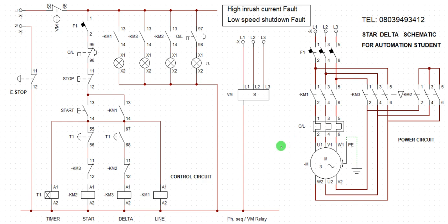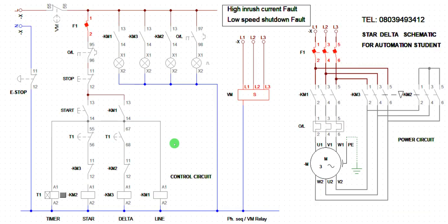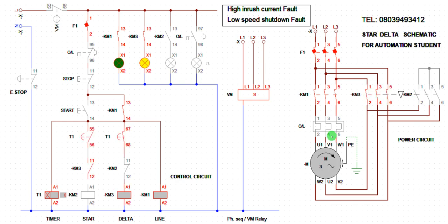Let's simulate this. I create the open circuit on the star contactor and put on the system. You can see the main contactor has closed and there is power, but the motor is not running because star is not energized. Now look — delta takes over and the motor starts with high in-rush current. The initial time the system was activated, the star contactor was not closed, so the system refused to run during timing. It then started with high in-rush power. That is the fault of this design.